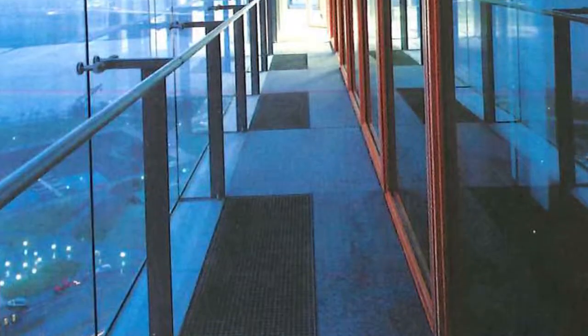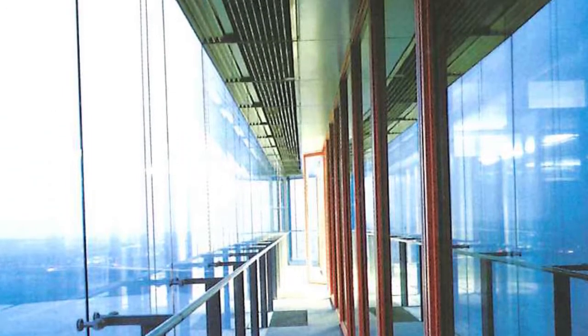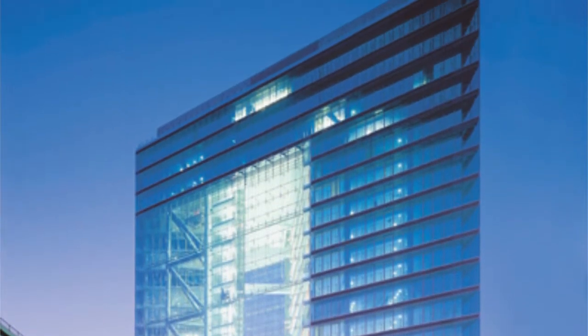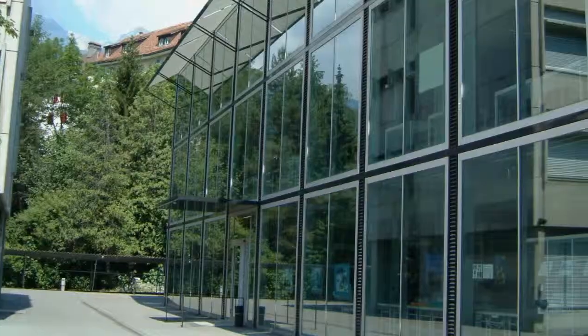A different project, for example the Clocktower in Düsseldorf, has a more active role for the double facade, where it is used to regulate the ventilation. It isn't just a buffer, it's a space in which outside air can heat up and eventually be used to ventilate the room in wintertime. In summertime, the air leaves the building through this double facade, effectively inverting the air streams.